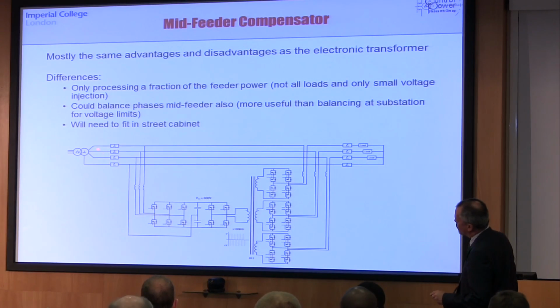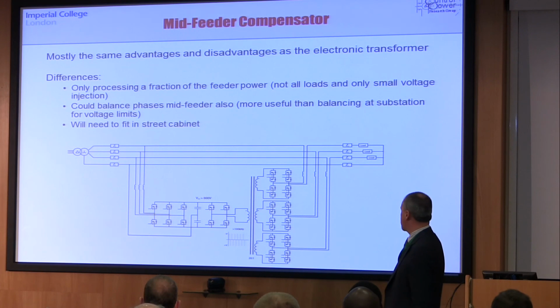But the shunt connection could be 4-wire, and this is the device that could do some useful work in terms of balancing current flows on the upper part of the feeder and indeed on that transformer. We could try to arrange a neutral current injection here that prevents or reduces neutral current flow in the transformer, which is a known problem.